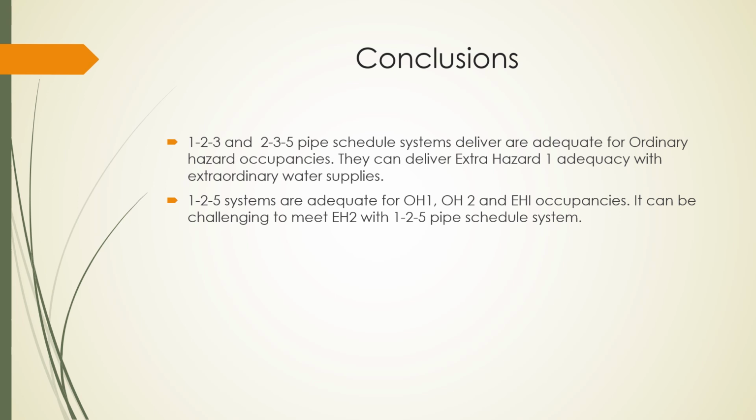That's a priority over a machine shop that's got a 123 system and it's got 50 psi at the riser. That may actually cut it, but it may not. But in the scheme of things, in the world where you need to prioritize, it's far more important to prioritize the solvent operation with the grossly inadequate system over the machine shop that may have a slightly inadequate sprinkler system.